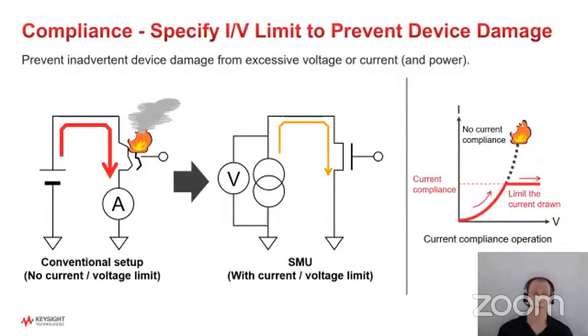Another important parameter to understand for parametric SMUs is we typically have a compliance setting for voltage or current. And in fact, sometimes they have a power setting as well. And so they'll shut off or stop the limit out at whatever is the lowest of those values you set, for either current, voltage, or power. But basically, that's just there to prevent your device from getting destroyed. Because again, applying sometimes too much current or voltage, especially if something breaks down, could destroy the device. And having the compliance setting will actually stop it from going any higher, and therefore prevent inadvertent device damage in situations. So make sure that you understand what the limits of your devices are, and that you set your compliance setting appropriately to prevent them from getting damaged.